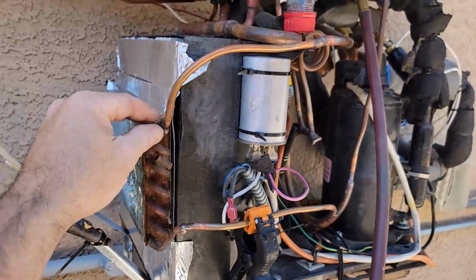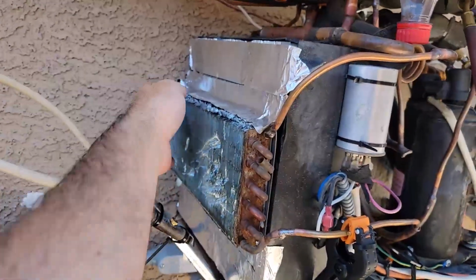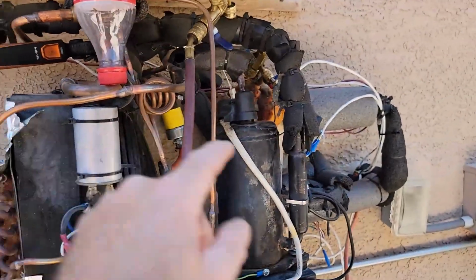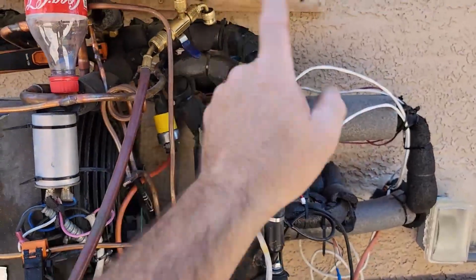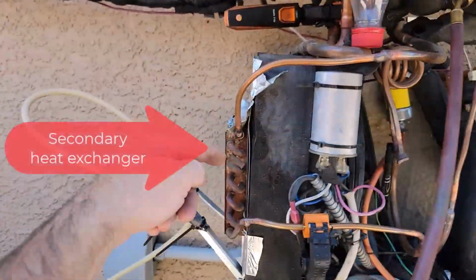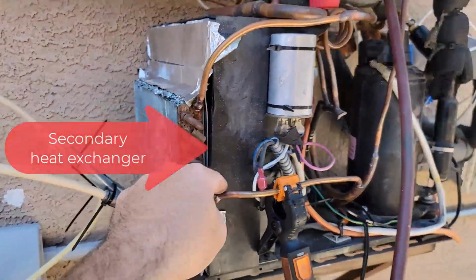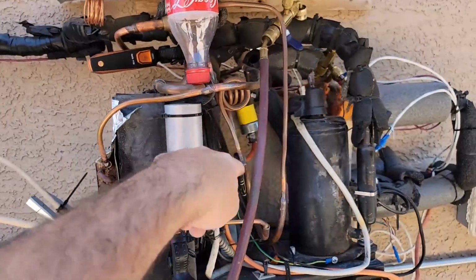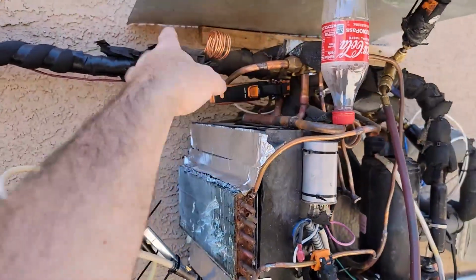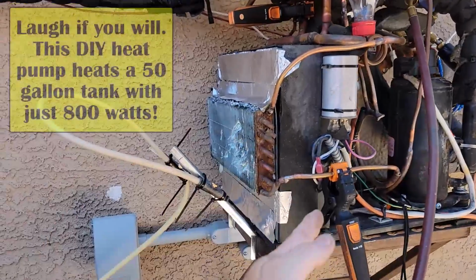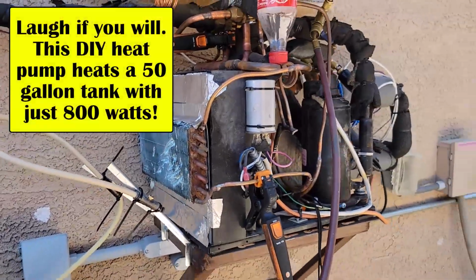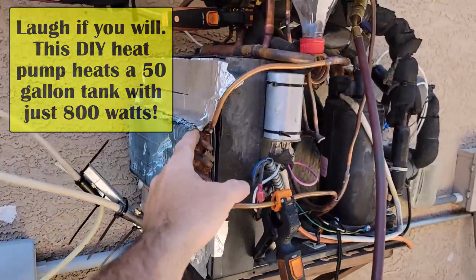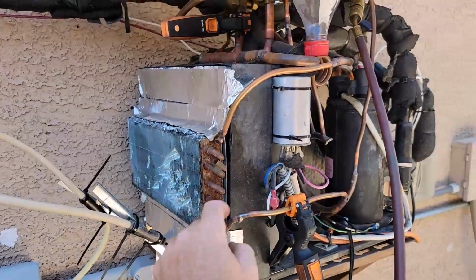When I redid it this spring, I threw in this extra little piece of coil. After the hot gas goes through the heat exchanger, it makes a pass through this small coil right here, and then goes back to the distributor for whichever metering device you use, an outdoor coil or an indoor coil for the summer.